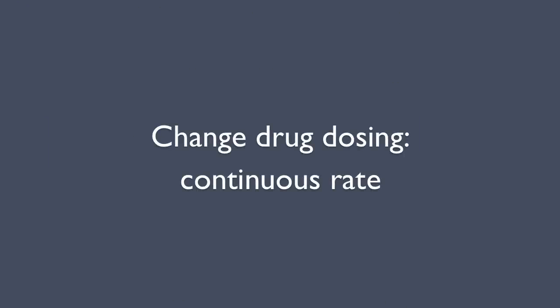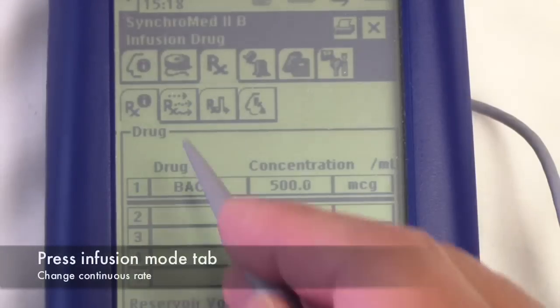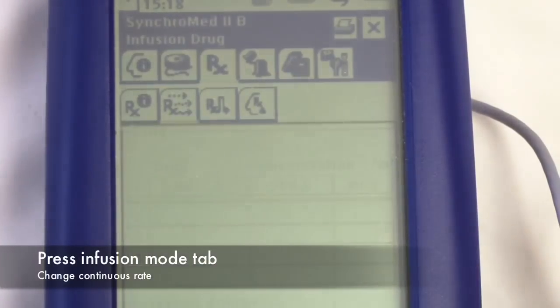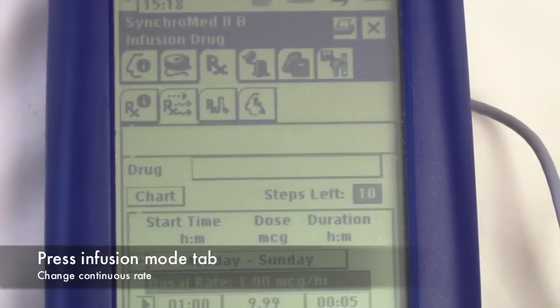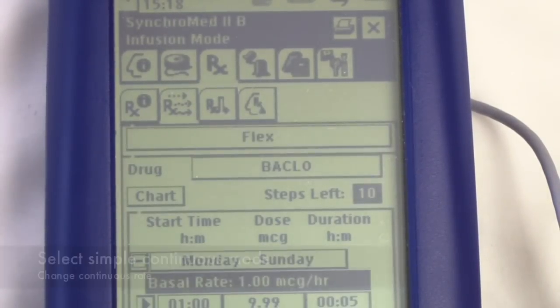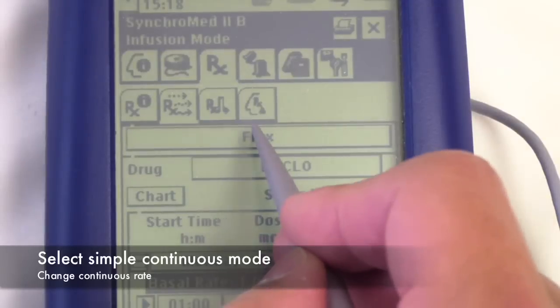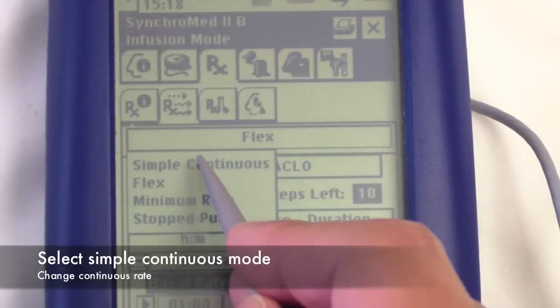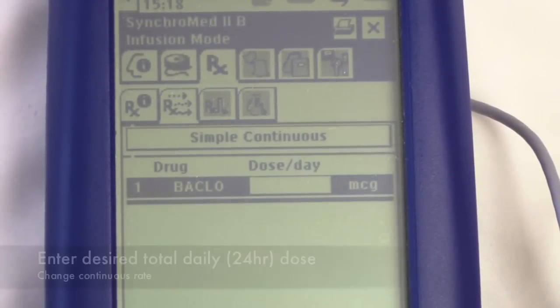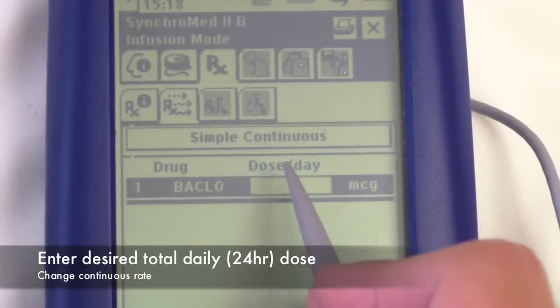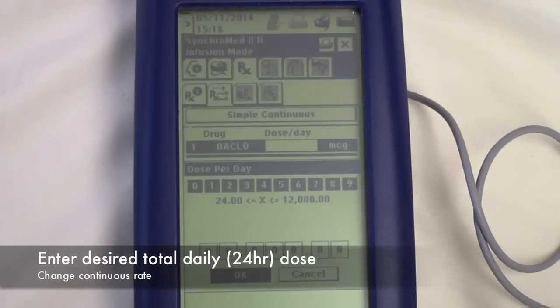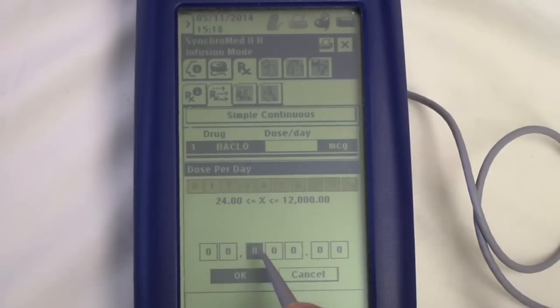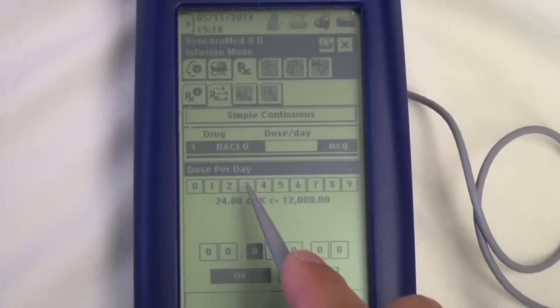To change the drug infusion rate, press the infusion mode tab towards the top. Simple continuous mode infuses the drug at a constant rate throughout the day. In this example, we'll enter a total of 300 micrograms to be infused over a 24-hour period.